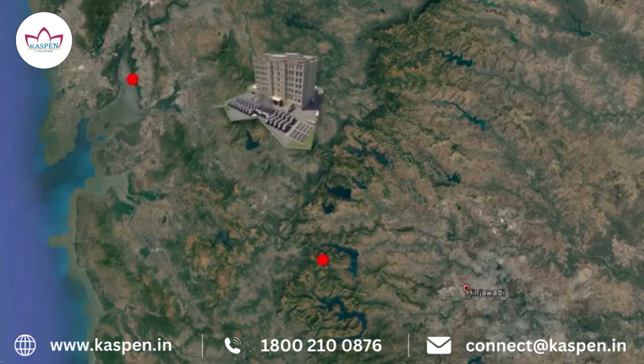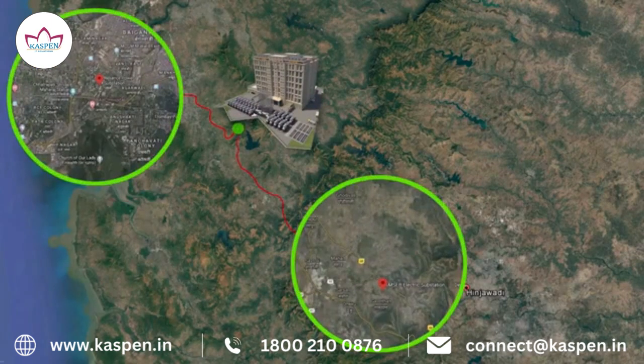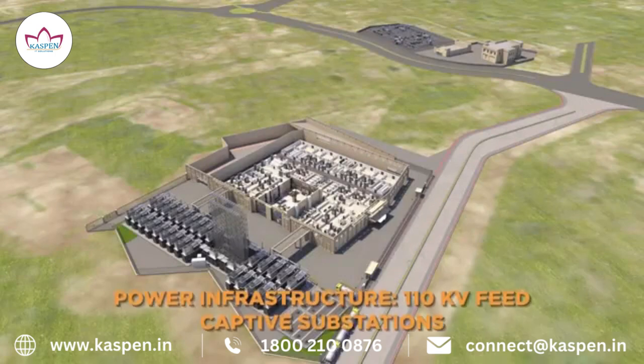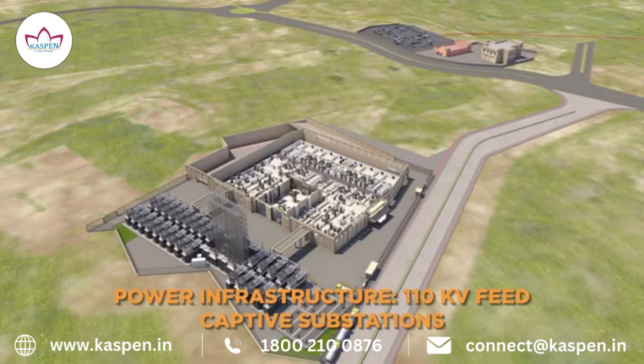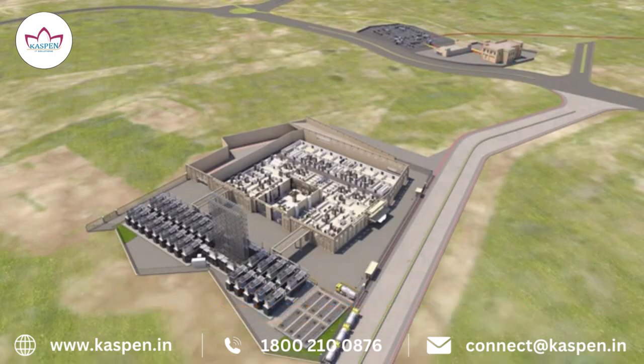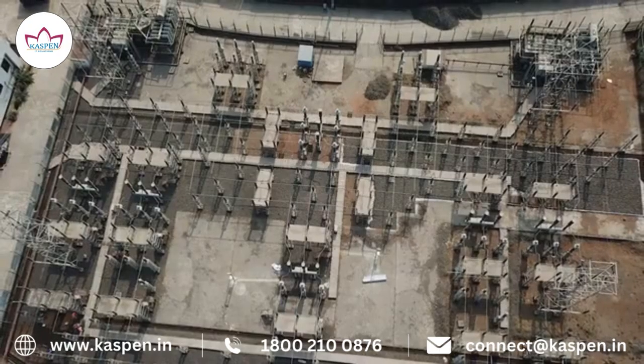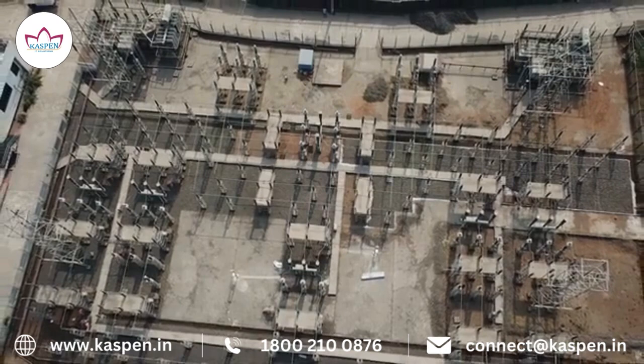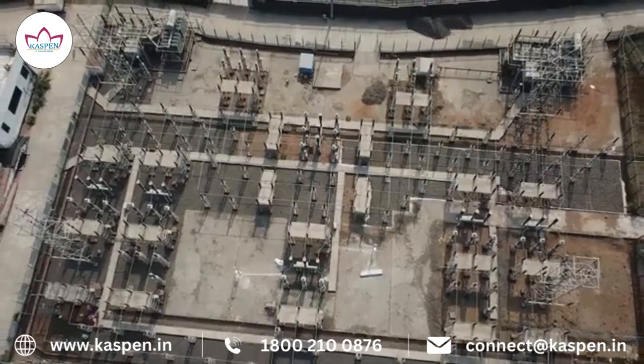Yotta NM1 receives power at 110 kilovolt from 2 upstream transmission substations and has a dedicated 110 by 33 substation and 33 by 11 substation right adjacent to the facility. 4 numbers of 11 kilovolt lines in N+N mode, each carrying 12.5 megawatt, supplies power to Yotta NM1. Our affiliate company manages the power distribution operations with a distribution license.